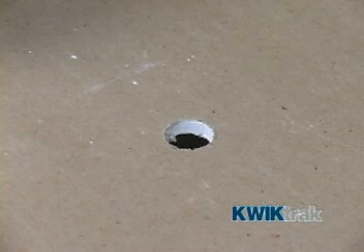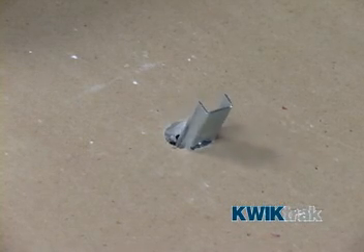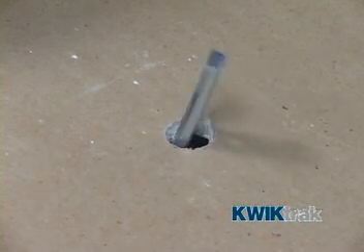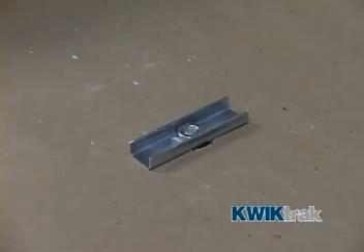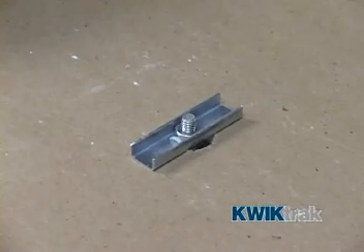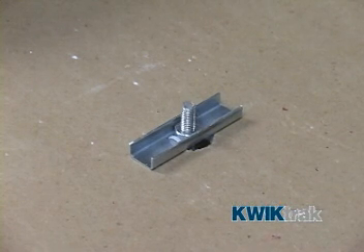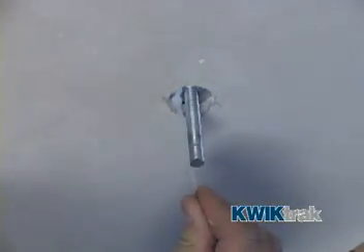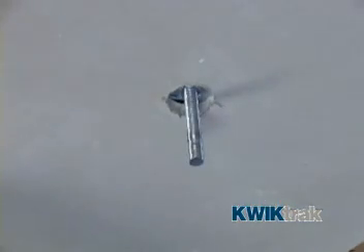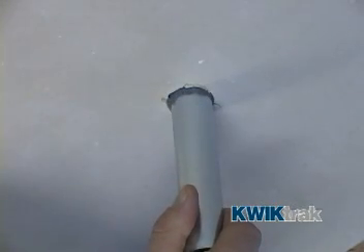If the suspended ceiling is constructed of drywall and access to the structure above is not possible, a pressure nut is inserted. While holding the nut with the attached zip tie, the rod is threaded through the pressure nut and up into the ceiling anchor. The pressure nut tool is used to back the nut down the rod until it is snug and providing support on the back side of the drywall.